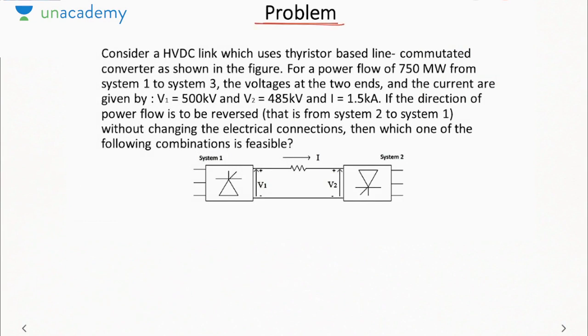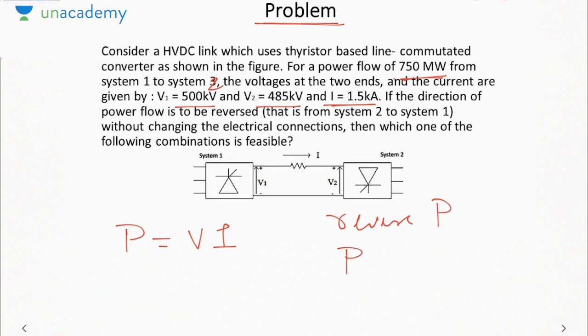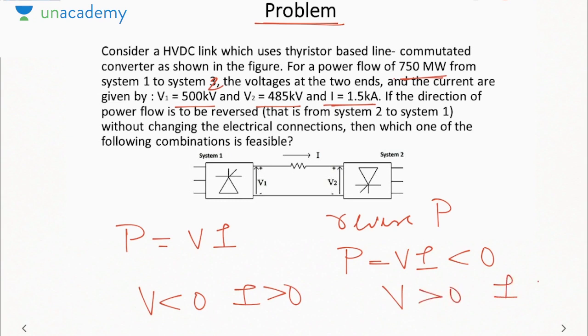Now let us consider a problem. Consider an HVDC link which uses a thyristor-based line commutated converter for a power flow of 750 megawatt from system 1 to system 2. The voltages at the two ends are given as V1 is 500 kV, V2 is 485 kV, and I is 1.5 kA. Now we need to reverse the direction of power flow without changing the electrical connection. Power in DC is given as P = VI. If you want to reverse power flow, then P = VI must become less than 0. Then either V must be less than 0 and I greater than 0, or V greater than 0 and I less than 0. That is, you have to reverse only one thing: either reverse the voltage polarity or reverse the current direction.